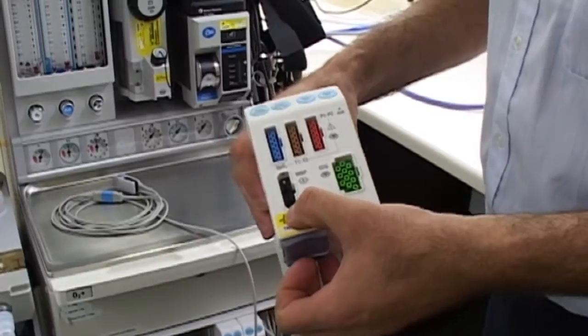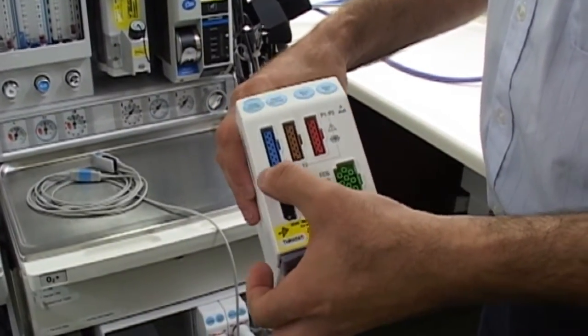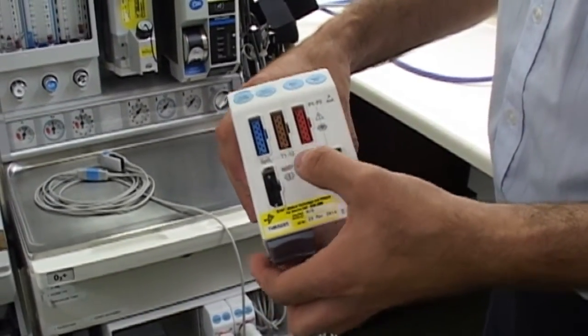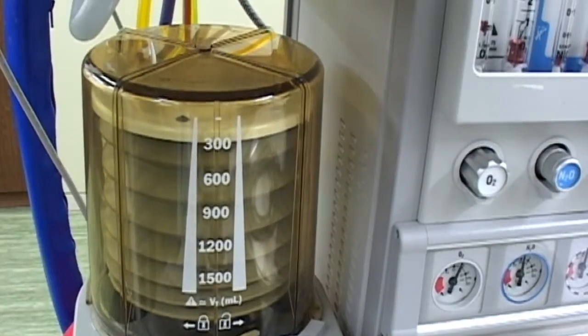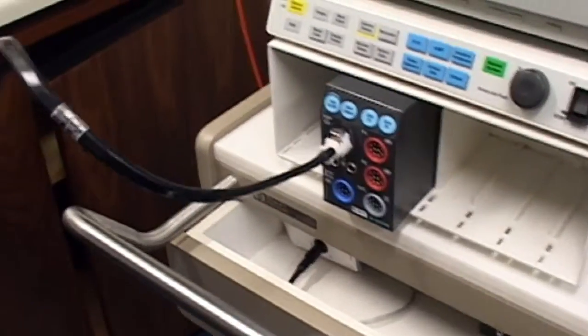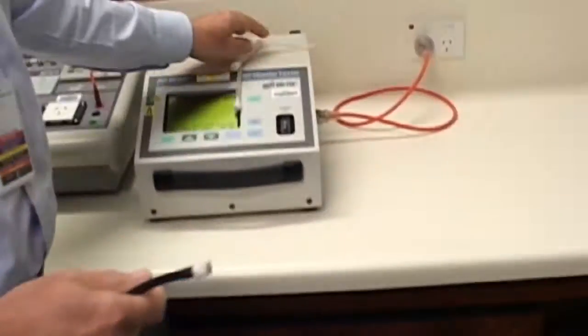So it'll measure your ECG, non-invasive blood pressure, your oxygen saturation, temperature and the invasive blood pressures. And we can check all those with our simulators, making sure the correct measurements are coming out, making sure they're accurate. And this is our tester.